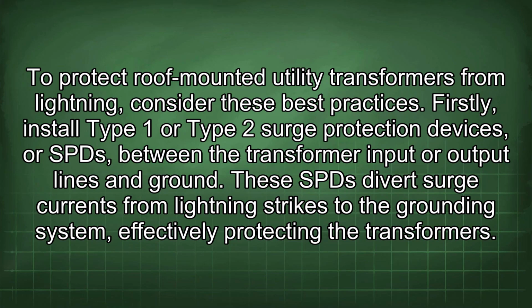To protect roof-mounted utility transformers from lightning, consider these best practices. Firstly, install Type 1 or Type 2 surge protection devices, or SPDs, between the transformer input or output lines and ground. These SPDs divert surge currents from lightning strikes to the grounding system, effectively protecting the transformers.